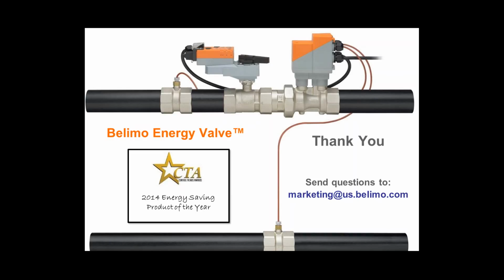Another question here is, in a data center, we have lots of air handling units fed by a chilled water system. We have intelligent control systems which optimize space temperature and switch air handling units on and off. How can we implement it? Note that it's very important, I'm so sorry, this is a long one, to have specific cooling requirements at each rack. So in what we would consider a data center, similarly to an emergency room or an operating suite, maybe an operating theater more than an emergency room, it's a critical temperature environment.